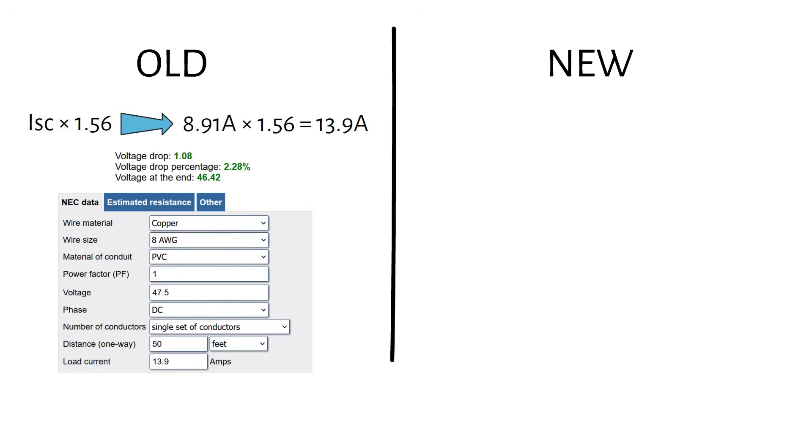I'm going to show you the old and new method, so you can see the difference. In my old method, I used ISC times 1.56 in the voltage drop calculation. So for this panel, it's 13.9 amps. So for the calculator, we enter the previously calculated voltage of 47.5 volts, a one-way distance of 50 feet and the current of 13.9 amps.